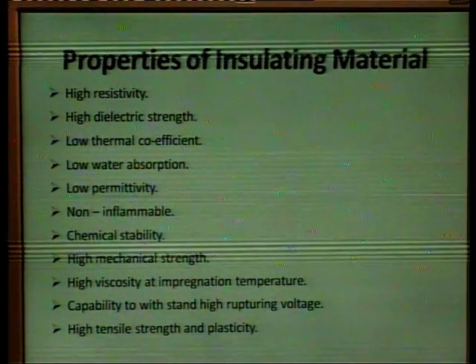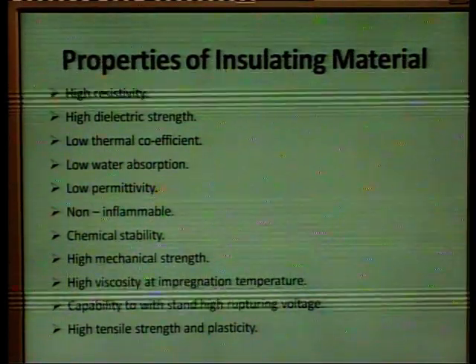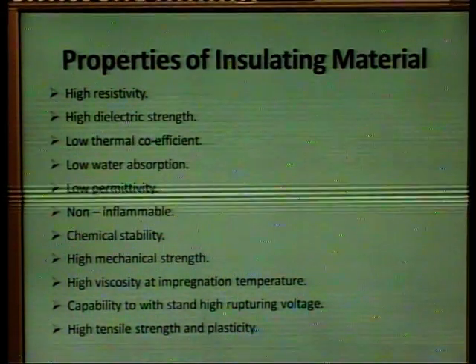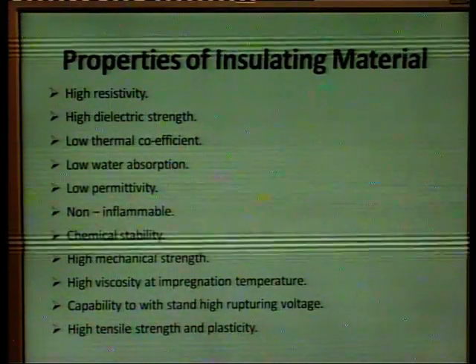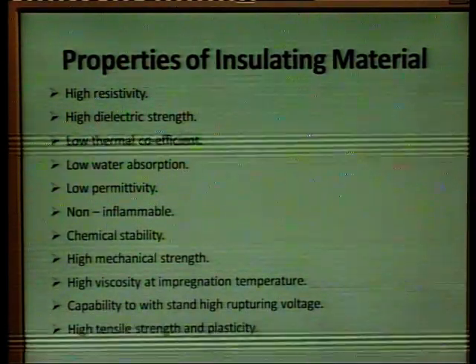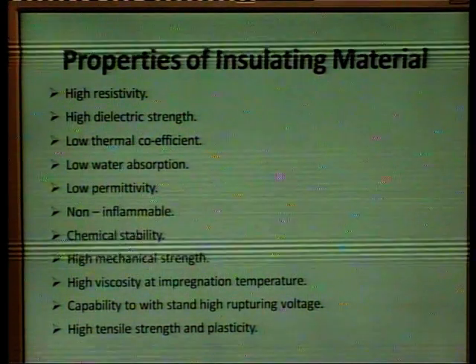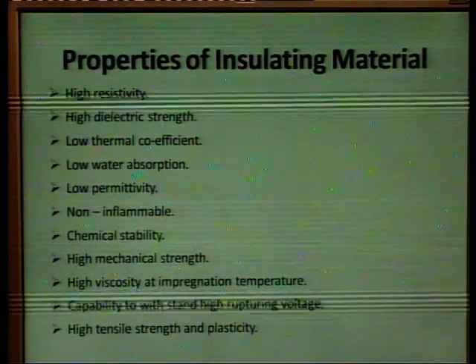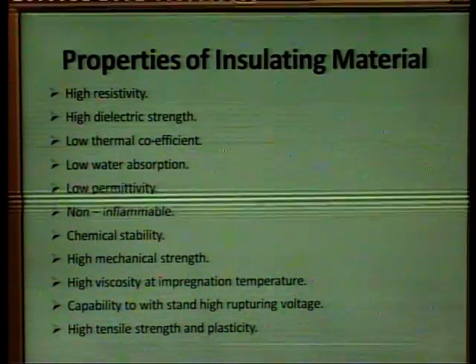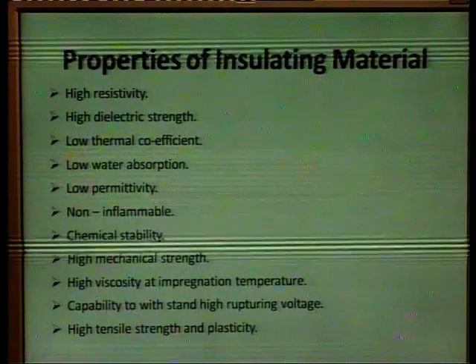Then the low water absorption should be there. The insulating material should have the property of low water absorption because water or moisture is very harmful for the dielectric strength of the material. Then it should have low permittivity. It should be non-inflammable. It should not catch fire easily. Then the chemical stability is very important because the cables are to be buried under the ground. So the chemical stability is a very important point.